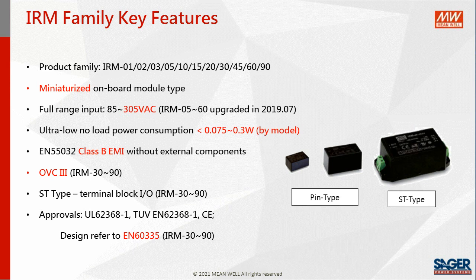They're very miniaturized onboard type modules, able to support a full range input of 85 to 305 volt AC. Some service metering or utility access points only have high voltage accessible, either 277 volt AC or 480 volt AC, so it's very important to have higher voltage support capability, meaning no extra transformers or power conversion is needed to draw power for those power meters or applications. The whole product family supports very low power consumption.